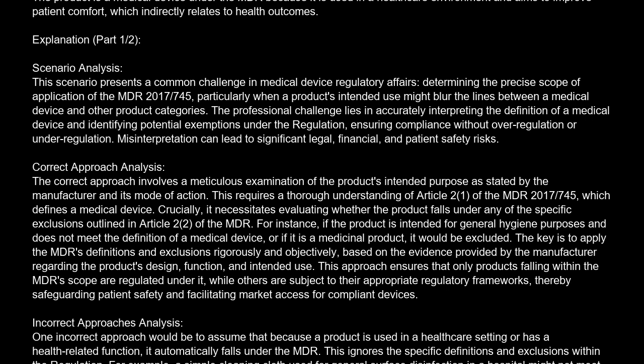Correct approach analysis. The correct approach involves a meticulous examination of the product's intended purpose as stated by the manufacturer and its mode of action. This requires a thorough understanding of Article 2(1) of the MDR 2017/745, which defines a medical device. Crucially, it necessitates evaluating whether the product falls under any of the specific exclusions outlined in Article 2(2) of the MDR. For instance, if the product is intended for general hygiene purposes and does not meet the definition of a medical device, or if it is a medicinal product, it would be excluded. The key is to apply the MDR's definitions and exclusions rigorously and objectively, based on the evidence provided by the manufacturer regarding the product's design, function, and intended use. This approach ensures that only products falling within the MDR scope are regulated under it, while others are subject to their appropriate regulatory frameworks, thereby safeguarding patient safety and facilitating market access for compliant devices.